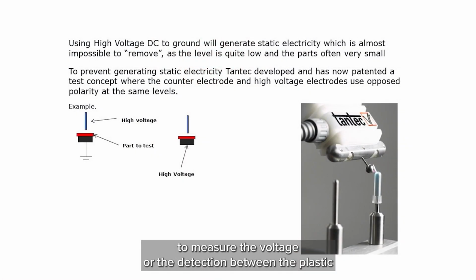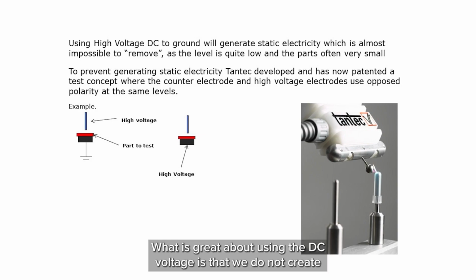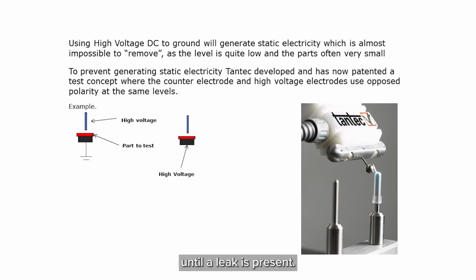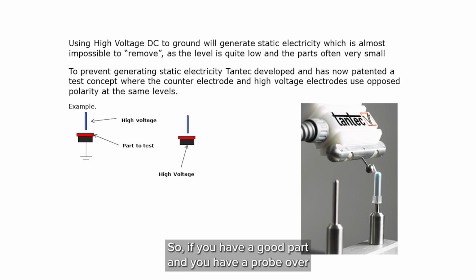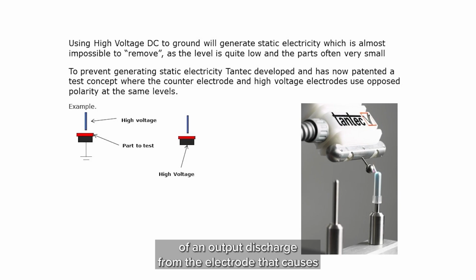So what we're doing here is we're using a DC voltage to measure the voltage or the detection between the plastic and the high voltage. What's great about using the DC voltage is we don't create any type of byproduct or corona or electrical discharge until a leak is present. So if you have a good part and you have the probe over the top of that, nothing is occurring in terms of an output discharge from the electrode that causes you to have to ventilate anything along those lines. When a detection is, or a hole is found and detection is present, there will be an arc that passes through to the metal, and then we provide that signal available to you through the generator.